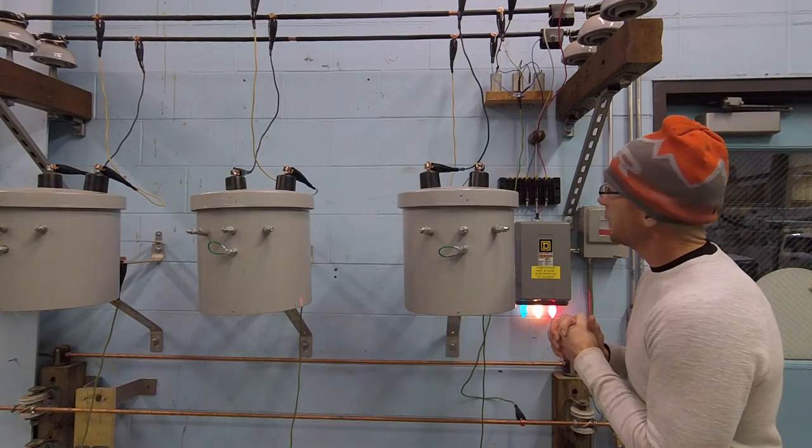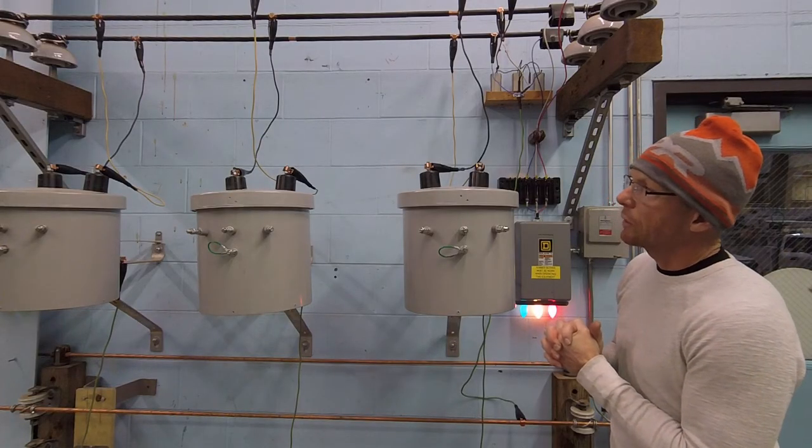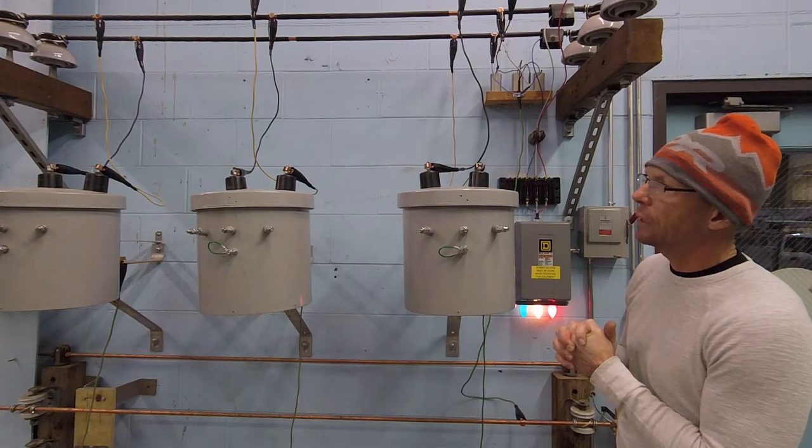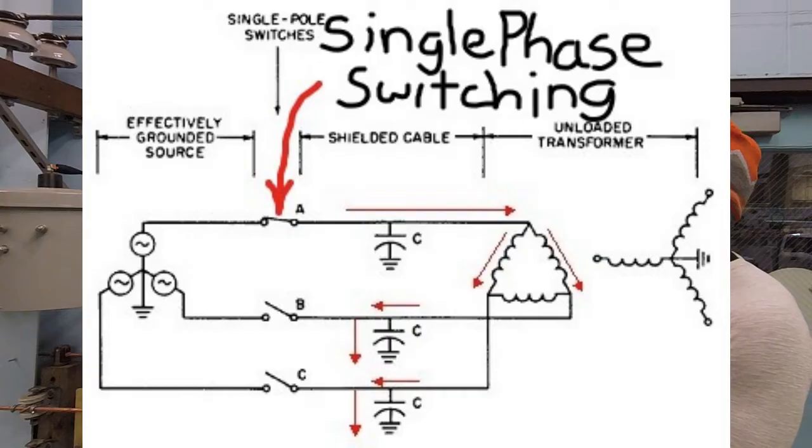But really a couple of things you need to do to create it, and the one that I think is the biggest culprit is single phase de-energizing or switching, or energizing for that matter, of three phase equipment, which is fed delta from an underground circuit.